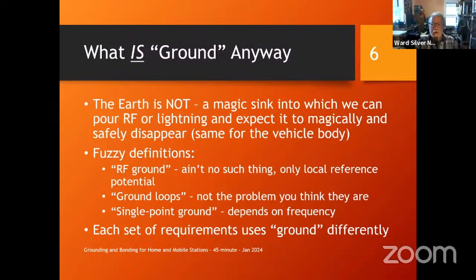Another term is single point ground. This really came out of the AC utility field, and what it means is an electrically small contact point so that current does not circulate within a power system. You're trying to connect everything together so that it's at the same voltage, which is a bonding thing we'll talk about. But the idea in AC was to prevent error currents from circulating in the system. So single point means electrically small. If you're at AC, 60 hertz, the wavelength is about 5 million meters, or 50 million, I think.